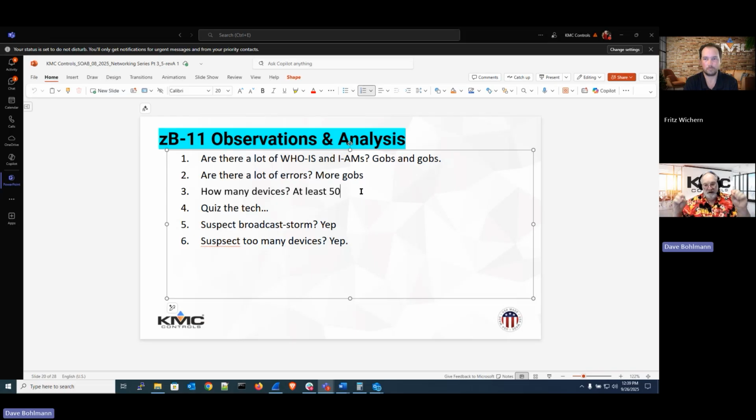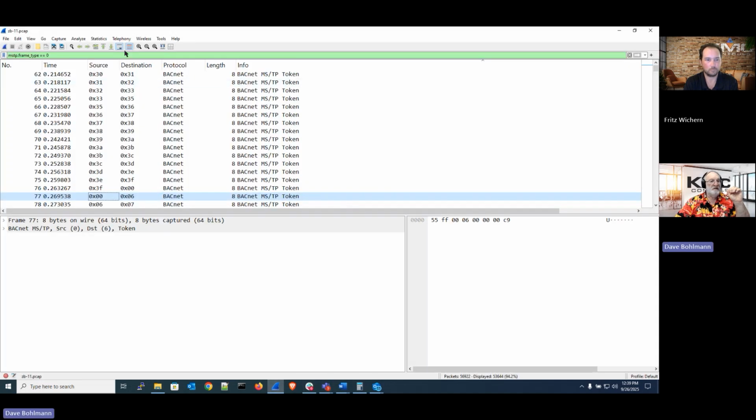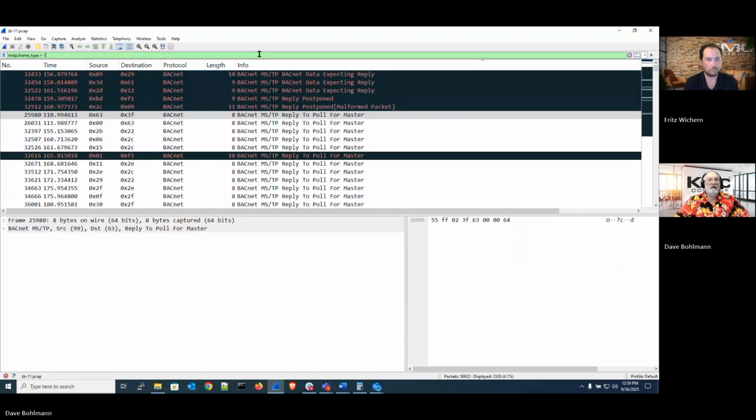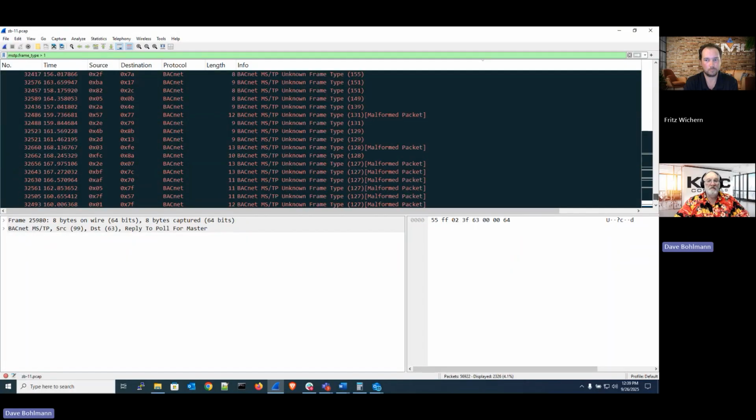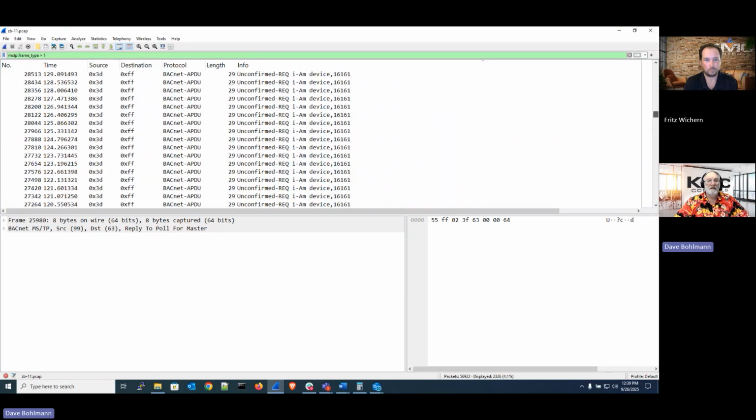Check your shielding. Make sure that's all correct, and then you can go back and redo a capture and see what your Who-Is and I-Ams are. If we go back to here again, do the info. So now let's see if we can find how many Who-Is and I-Ams we got. Man, there's a lot of errors.